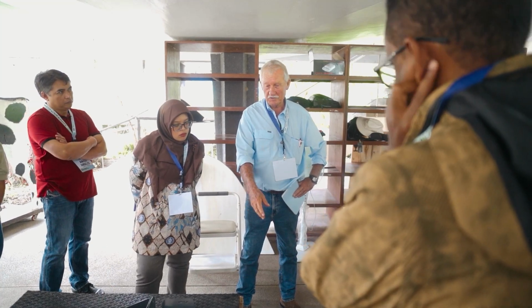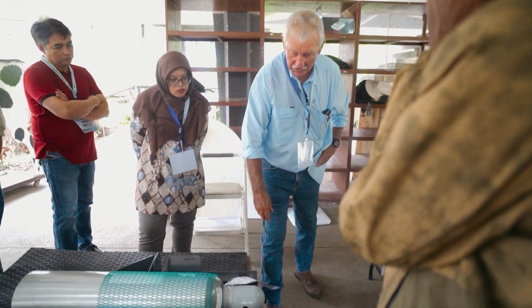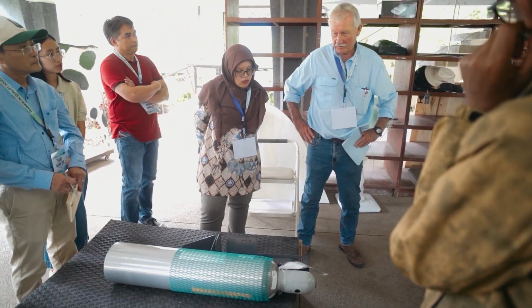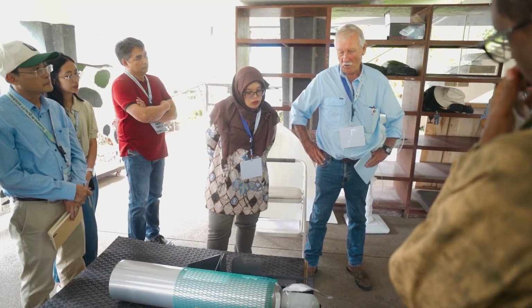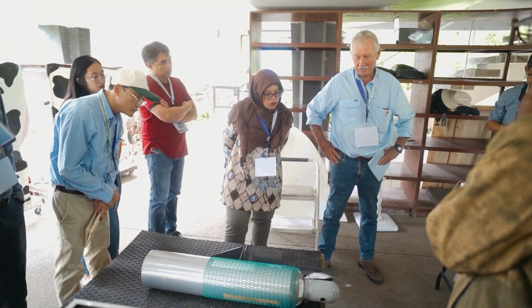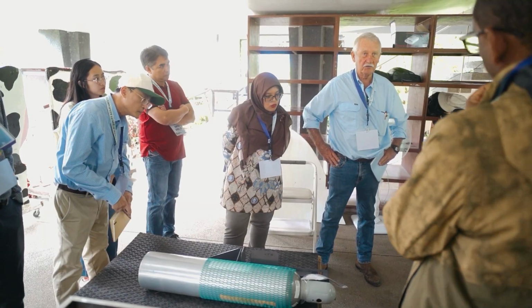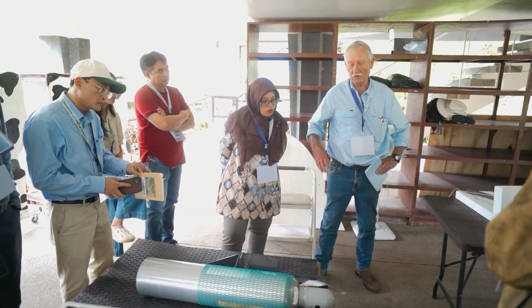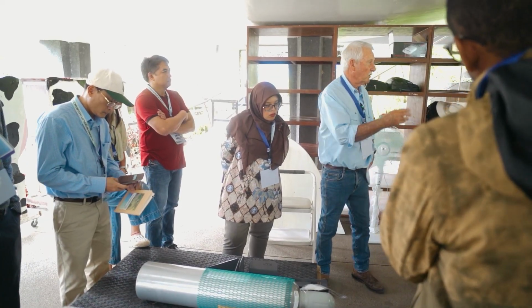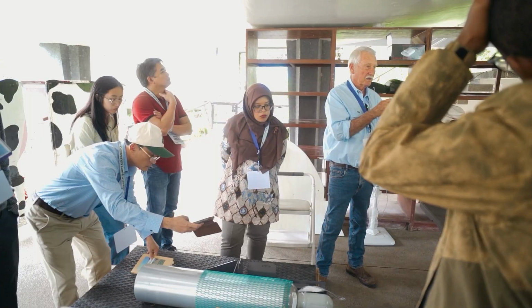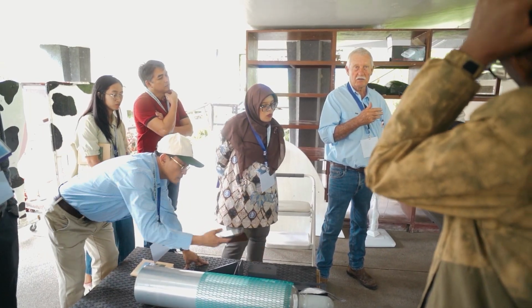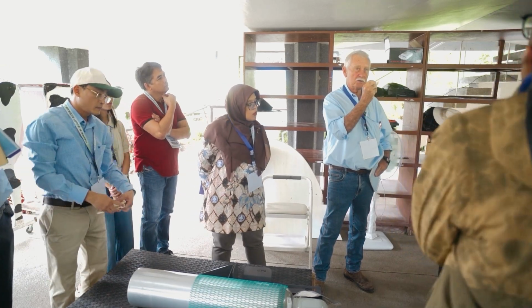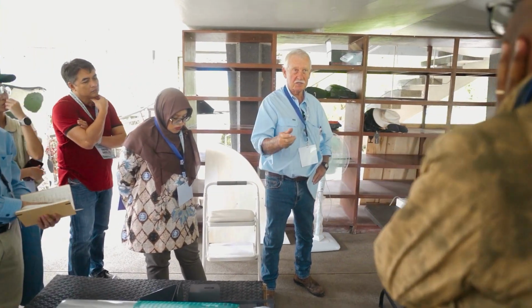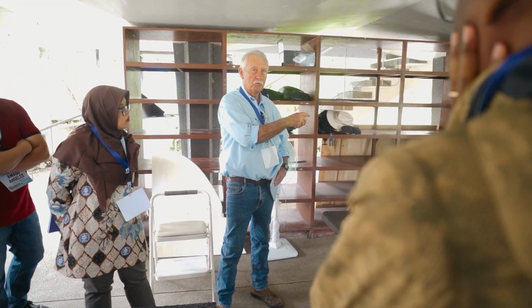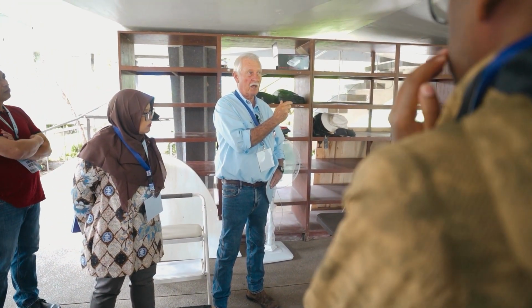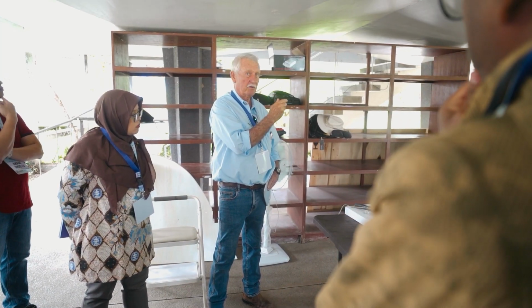The new system has this cylinder, which is a combination of all the gases that we use, but at hugely high concentrations. And how this works, we'll get to when we look at the unit. It has a mass flow controller that will inject a certain percentage of these gases, mixed with ambient air, to produce what they require as a span and a zero gas.